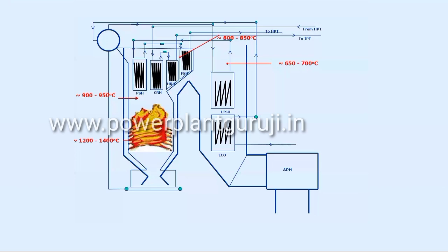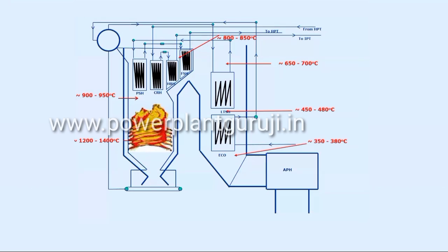LTSH inlet temperature will be in the range of around 700 degree centigrade. Then economizer inlet will be 450 to 480 degree centigrade. Then after the economizer, that is APH inlet will be around 350 to 380 degree centigrade. And the exit temperature, that is boiler exit temperature, APH outlet gas temperature will be in the range of around 130 degree centigrade.